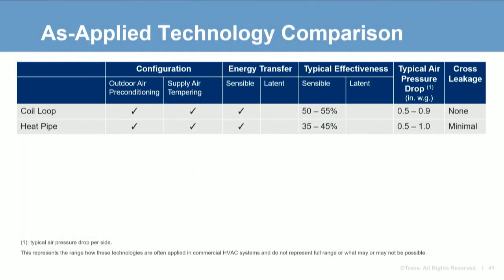Adding heat pipes to the comparison table: heat pipes can be used to precondition outdoor air in a side-by-side configuration. Some manufacturers also provide configurations wrapped around a cooling coil, providing supply air tempering. Heat pipes transfer sensible energy but no latent energy. Sensible effectiveness is very similar to coil loops at 35 to 45%, air pressure drop is fairly similar, and heat pipes generally have minimal cross leakage.